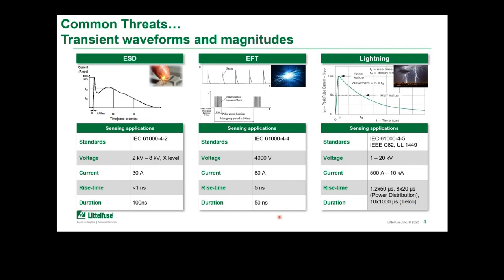The load switching standard, the most common one used here, is the IEC 61000-4-4. And this consists of very rapid pulses, but they are grouped together in what's called a burst pulse. And so this actually provides a little bit more energy than you would see basically in your ESD type of event. And these voltage levels can range up to 4,000 volts and have considerable amperage involved with them. And then this is reoccurring. So this is essentially to try to simulate contact bounce within a switch.